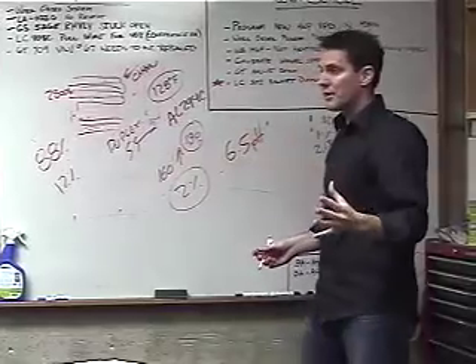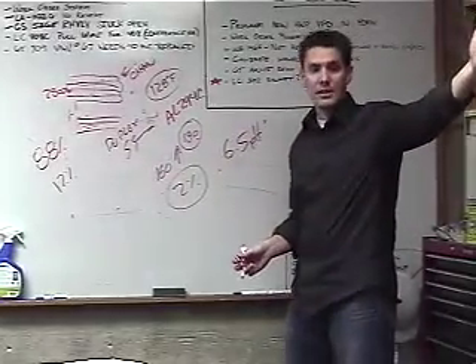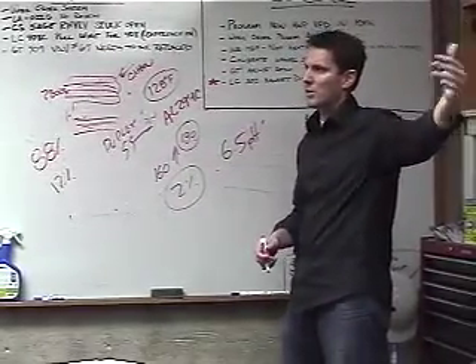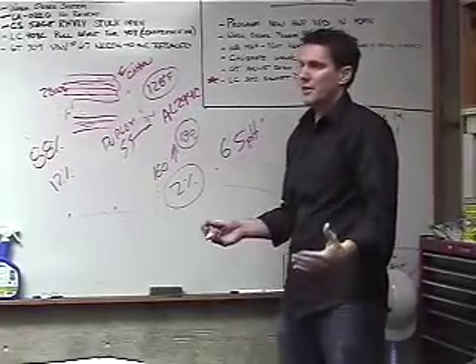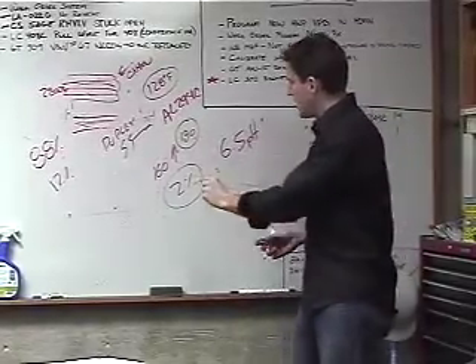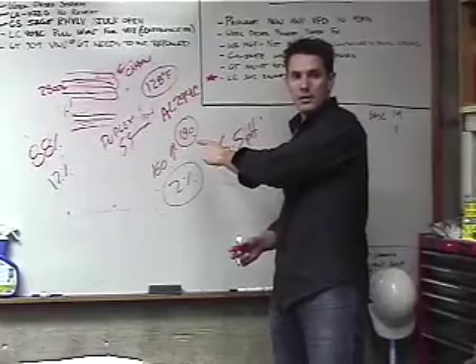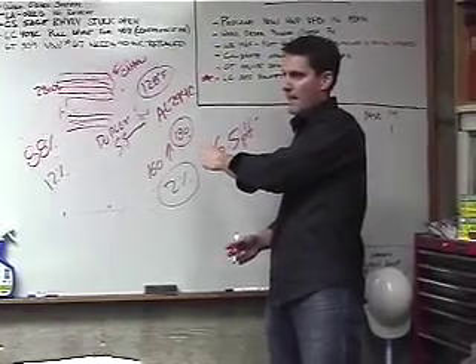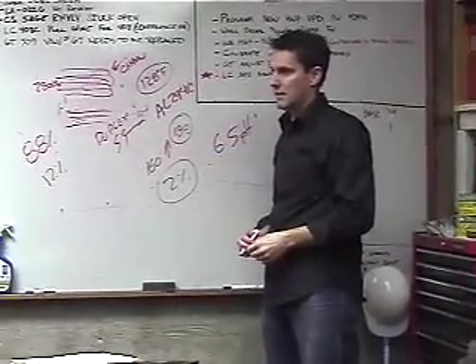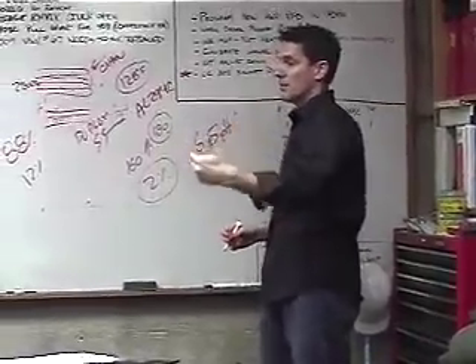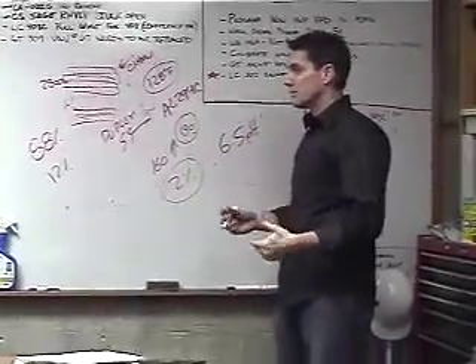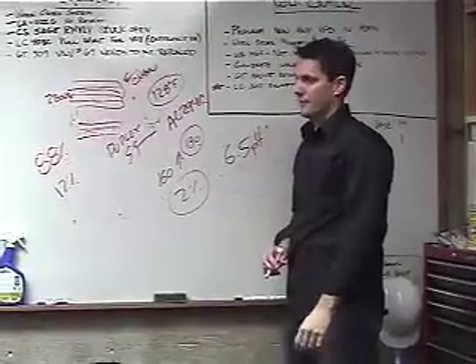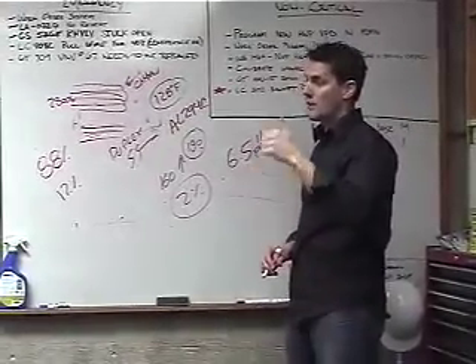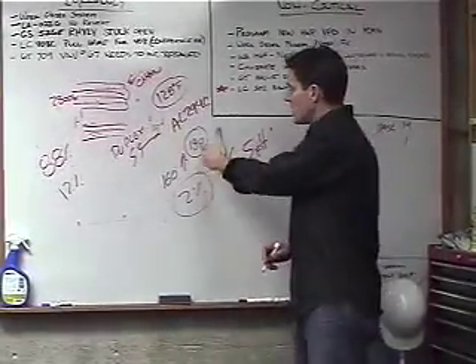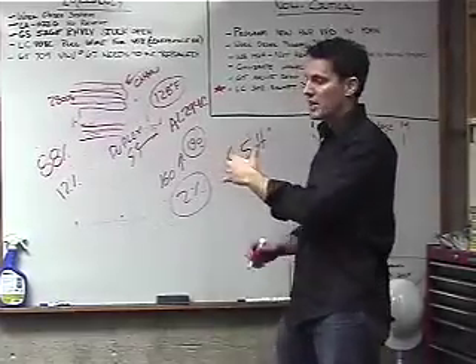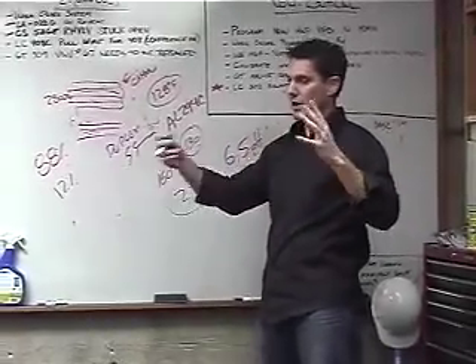But the whole rest of the year, heck, today we probably need heat. Today's a little colder, but yesterday it was 45 degrees, 50 degrees. We still need heat, but do I need 180 degree water? Well, this plant's a little bit unique because we don't run it more than 150. So your return water temperatures are coming back 90. Perfect, which is why you've got the condensing boilers in here. Resetting our water temperatures is big. Resizing heat exchangers, coils, whatever, for colder.